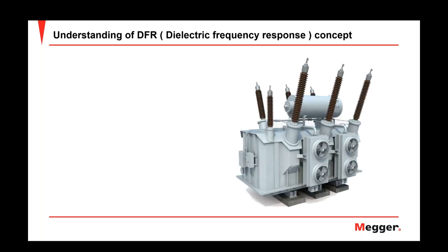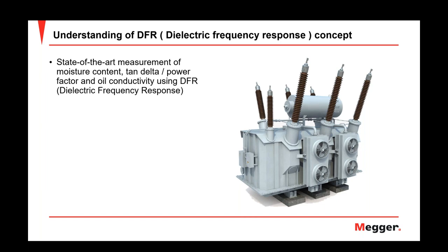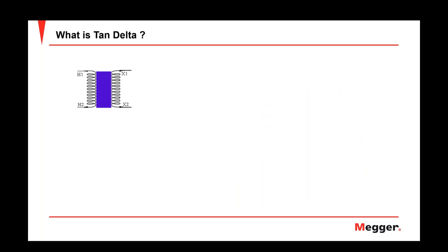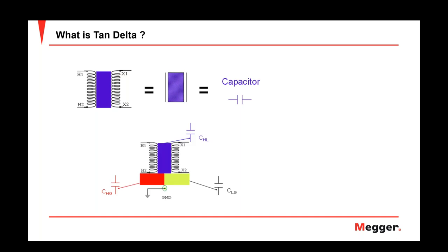Starting with transformers — one of the state-of-the-art measurements of moisture content is making tan delta as a power factor or oil conductivity assessment using DFR, or Dielectric Frequency Response. So what is tan delta? If we assume we have two windings with insulation in between — as is typical in a transformer — and we look at that insulation as an electrical element, it behaves like a capacitor.